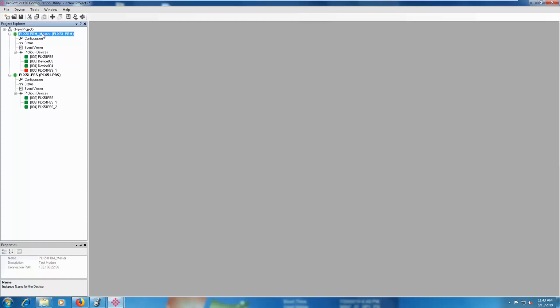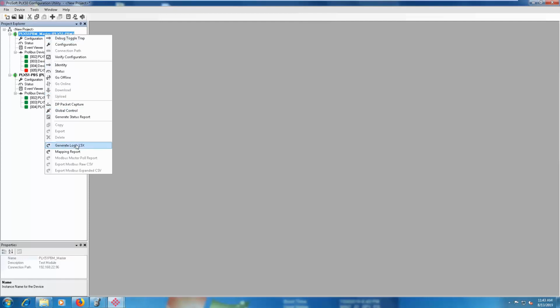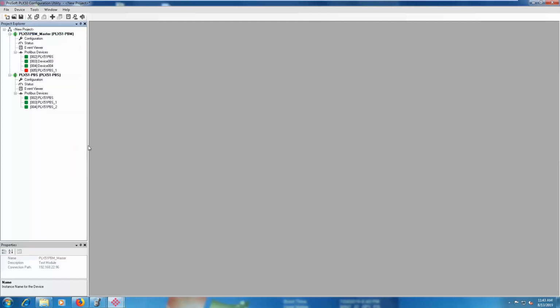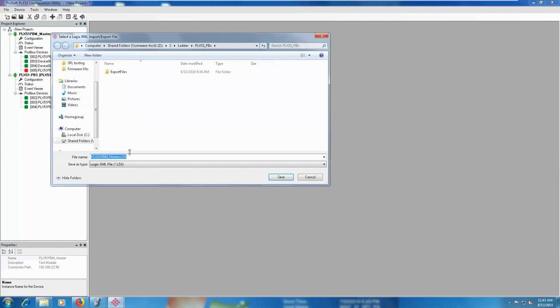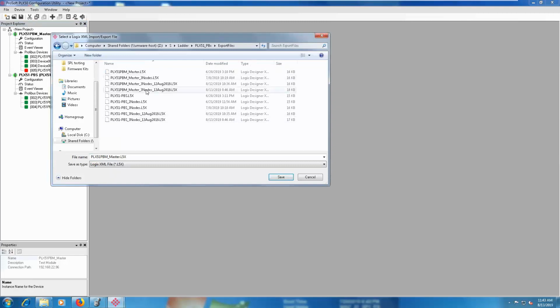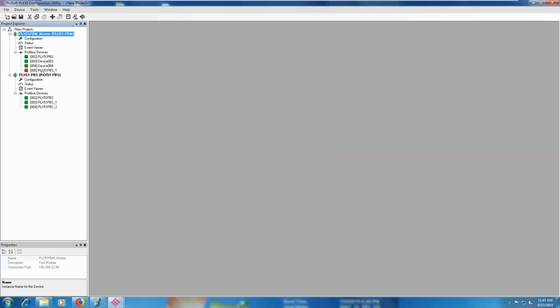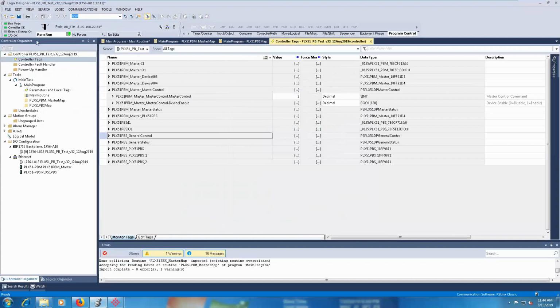As far as exporting your configuration files, as you add a new device into the project, you could go ahead and utilize the Generate Logix L5X. This will give you the ability to create a new export file, and I'll save it with a new name and put it right here, and save that. Now I've got an L5X file that I can then import into my Studio 5000 environment.